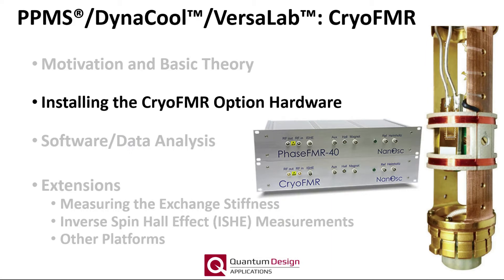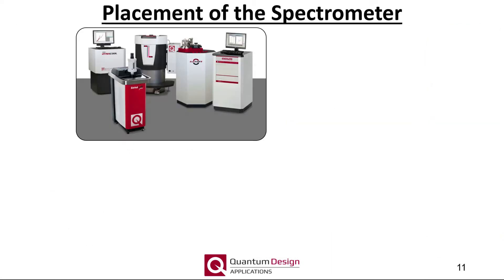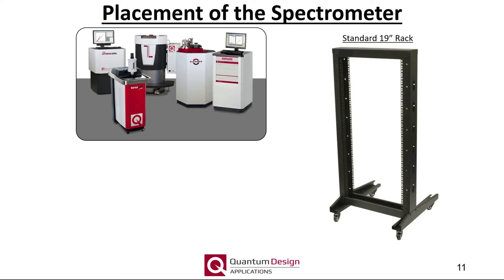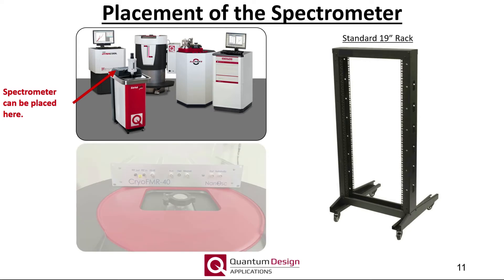On to installing the cryo-FMR option hardware. Our family of PPMS systems represent a wide variety of form factors. Furthermore, the instrument box from NanOsc is not one of our usual CAN-based modules that you may be familiar with, which can make placement of the spectrometer sometimes challenging, especially since the included RF cables are only 36 inches long. That being said, the spectrometer can easily be mounted within a standard 19-inch rack, as shown here. Additionally, for the VersaLab, it can be simply placed at this location, or for the Dynacool, which will be shown in the following slides, the instrument can simply be placed at the top behind the sample chamber, as shown here.